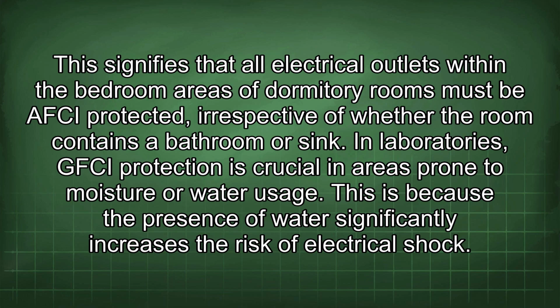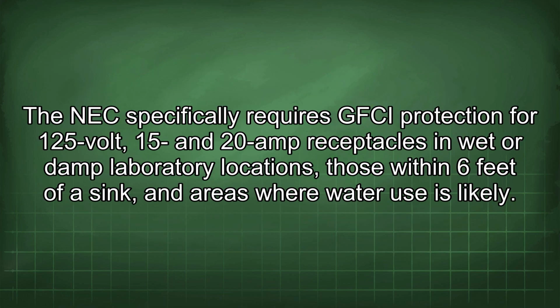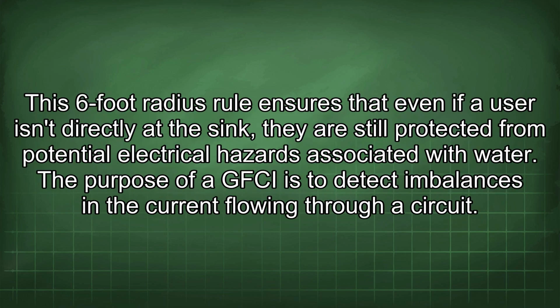In laboratories, GFCI protection is crucial in areas prone to moisture or water usage. This is because the presence of water significantly increases the risk of electrical shock. The NEC specifically requires GFCI protection for 125 volt, 15 and 20 amp receptacles in wet or damp laboratory locations, within 6 feet of a sink, and in areas where water use is likely. This 6-foot radius rule ensures that even if a user isn't directly at the sink, they are still protected from potential electrical hazards associated with water.